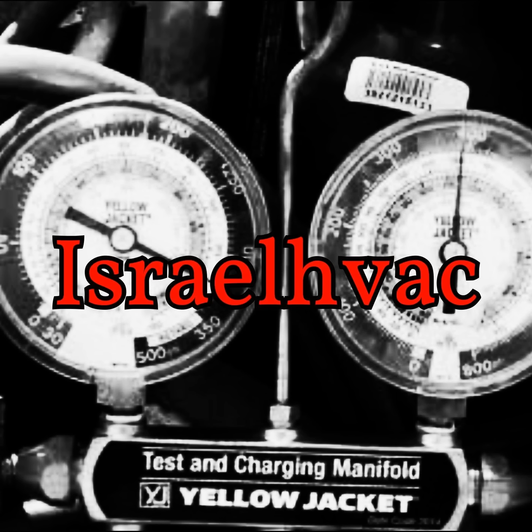So I popped on the Z manifold, or the C manifold, the cowboy manifold that me and Zach have. And the compressor had bit the dust. She was running, but she wasn't pumping. We had equal pressures. We had 150 over 150.